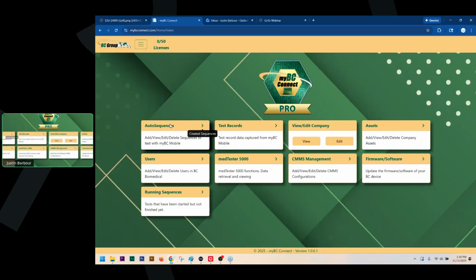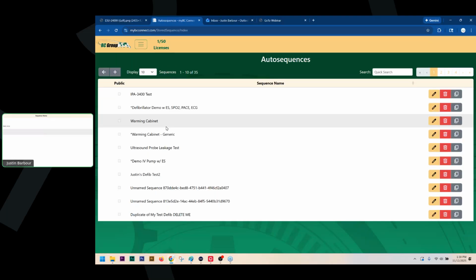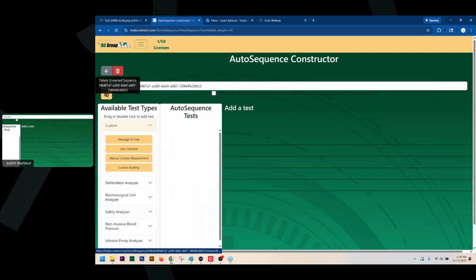Let's go ahead and take a look at all the different types of medical devices that we can test through automated testing. So let's create a whole new sequence right here, and let's go right from the top. Message to the user. You can give a message to the technician like, this device is under contract, do not adjust anything, etc. You can give them that warning or that prompt as soon as they scan that barcode, it'll pop up.